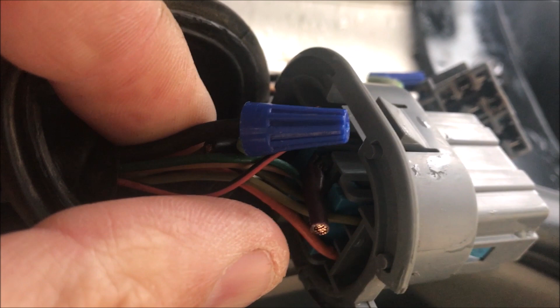So the root cause of the problem with the motor not working was that it had no ground. The solution is to just run a jumper wire. In this case, it's that green wire. I cut the ground on the back side of the plug.